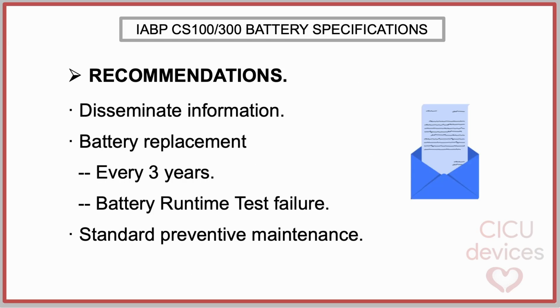Finally, Datascope recommendations are as follows. Healthcare institutions should ensure that this information is effectively disseminated to all current and potential users within the organization. Batteries must be replaced every 3 years, or earlier if they fail the battery runtime test during scheduled preventive maintenance. Standard preventive maintenance procedures should be continued as recommended, with no additional testing requirements beyond those already specified in the manufacturer's documentation.